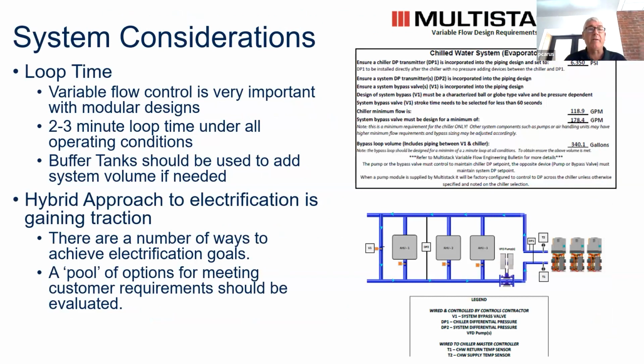Important system considerations: loop time critical. Got to make sure we have a big enough loop and long enough to manage the process so that we don't get into cycling. If you don't have enough loop time, buffer tanks are always a reasonable option. The stuff that you see on the right is what we do for our customers so that they understand minimum loop time, system bypass design, where bypass valves would be. Those kinds of things are all part of the selection process that the guys from Long have access to.